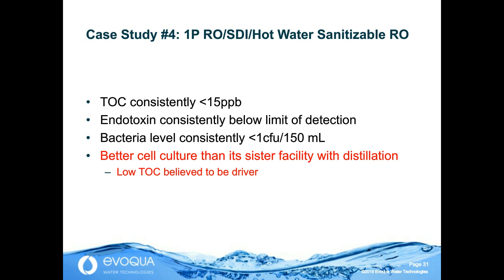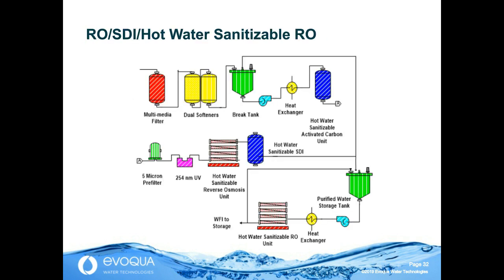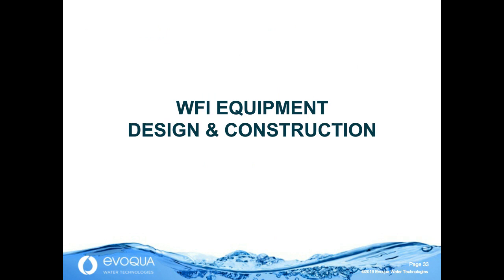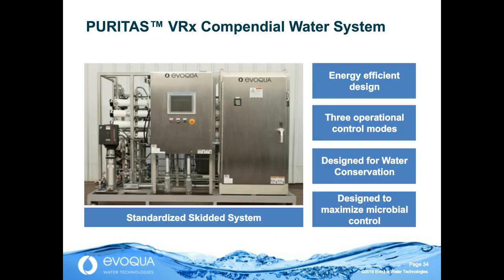And that system had pre-treat, hot water sanitizable RO, off-site regenerated resin that could be hot water sanitized, then to a tank heated and through the final hot water sanitizable RO, and a very successful production record for water for injection. We're going to very quickly look at equipment in the interest of time. If we look at this system, this is an Evoqua VRX platform, but we're talking about the attributes.